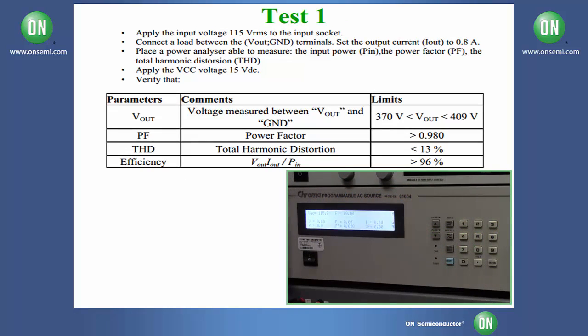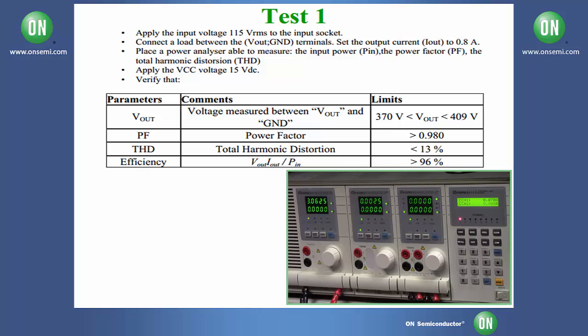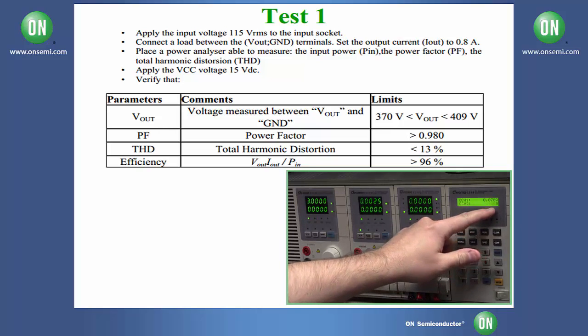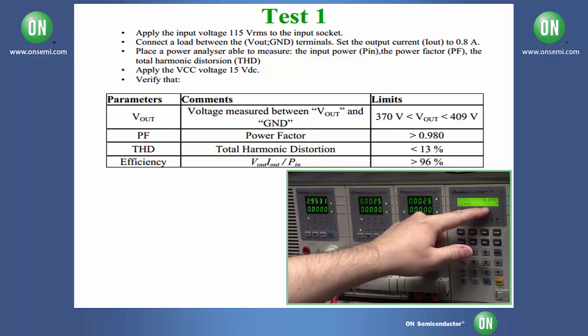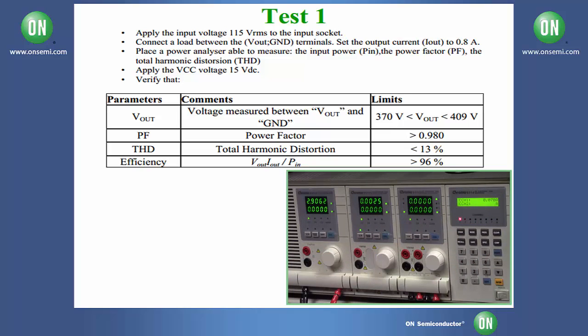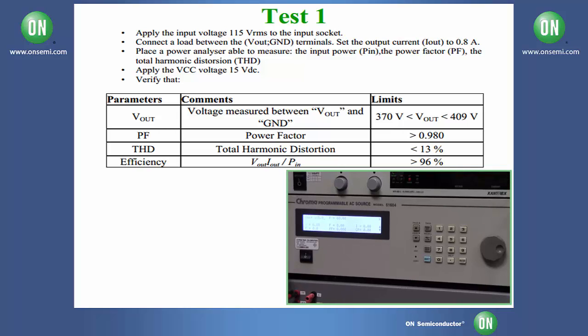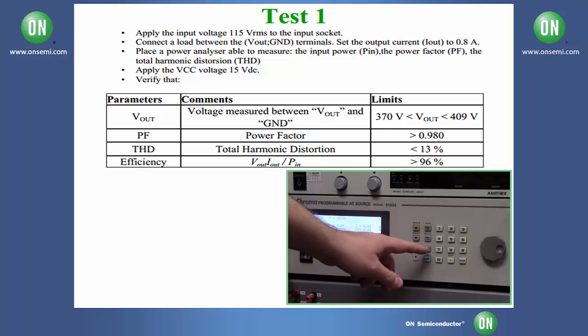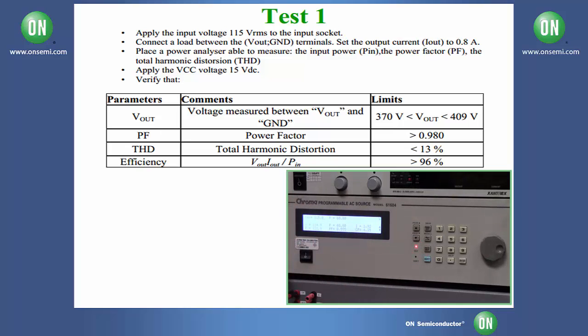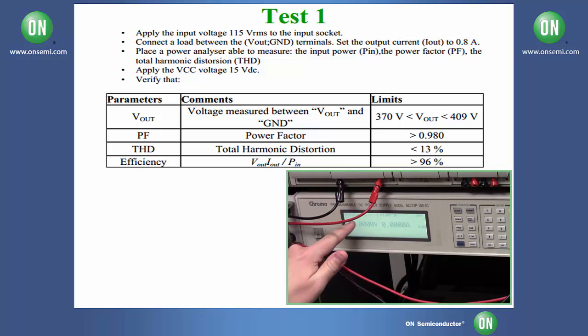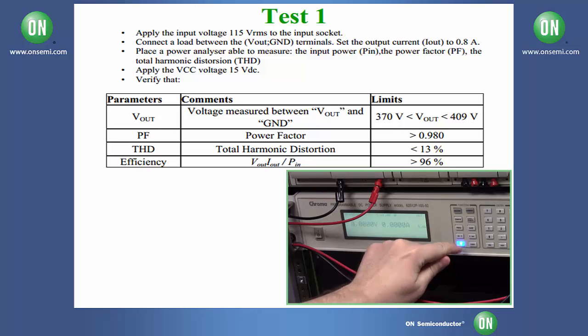To begin test 1, first we're going to make sure that we have our AC source set to 115 volts AC, 60 Hertz. Next we're going to make sure that our DC electronic load is set to 0.8 amps or 800 milliamps, and we're going to turn that load on. And once our load is applied, we're going to power up our board by first turning on our AC source, and then we're going to once again make sure our VCC bias voltage is 15 volts and turn it on.